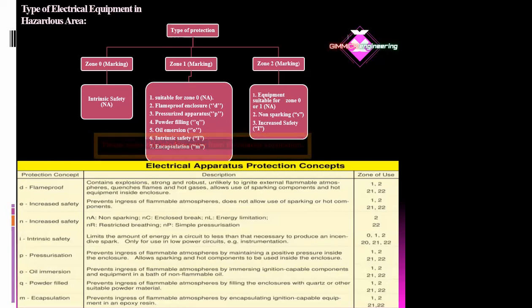In some places you will find n. N indicates non-sparking. Okay. If you find i, it refers to intrinsically safe, which we normally use on instruments. Right now we are going for intrinsically safe or ATEX approved instruments. In this the voltage level is very low, which is used to reduce sparking. And if the area is zone 21 or zone 22, that is a powder processing area, then you will find the letter p, where positive pressure is maintained inside the component, so the intensity of sparking or ignition can be reduced.